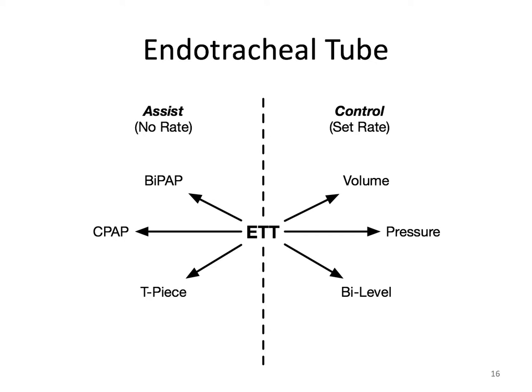There are two major classifications of things we can do with the ventilator. On the assist side, we can set the ventilator to perform BiPAP, CPAP, or T-piece — where T-piece refers to tube compensation only, allowing the practitioner to determine if the patient is able to wean. All of these modes on the assist side have no set rate and give the patient more control, just with some assistance. On the control side, there is always a set rate; you can control for pressure, volume, or bi-level, which integrates features of both pressure and volume control.